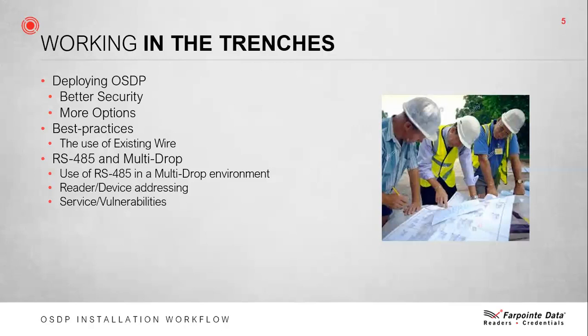Regarding addressing: if you utilize multi-drop deployment, readers must be assigned addresses so they can be identified within the loop. This address is assigned via OSDP tools from the controller. It's also important to understand that not all controller manufacturers will provide the same capabilities — some limit their multi-drop spec to eight devices, and others only support OSDP in point-to-point topology. Regarding service and vulnerabilities: if you experience a line break within a loop of devices, any device wired past the break would cease to operate. This means the difference between one door being down versus several doors being down — though you have to ask yourself how often you actually experience these types of line breaks.